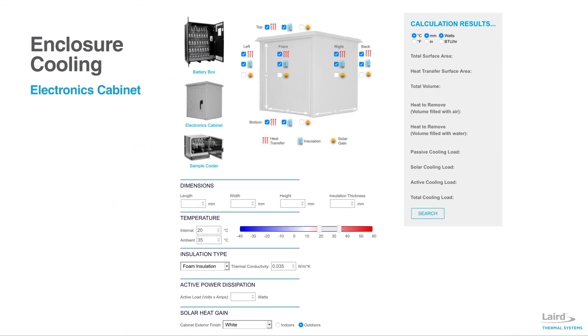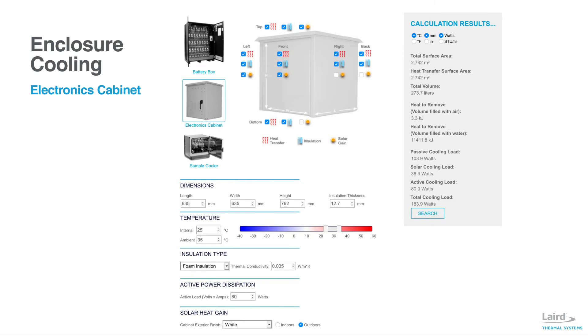In this example, we will use the enclosure cooling calculator to find the requirements of cooling a box of electronics. The first step is to select the example nearest your application, which in this case would be the electronics cabinet. In this view, you will notice that there are multiple sides to control heat transfer, solar gain, and also whether it has insulation or not.